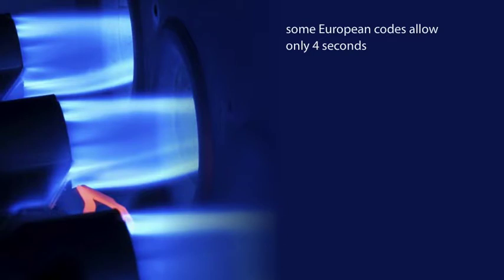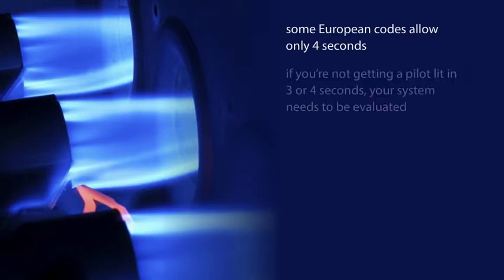Actually, it should never really take 10 seconds. If you're not getting a pilot lit in 3 or 4 seconds, your system needs to be evaluated more closely. This is an important startup consideration. Once pilots start to approach 7 or 8 seconds to light, they can be audible and the condition can be an indicator of something going very wrong.